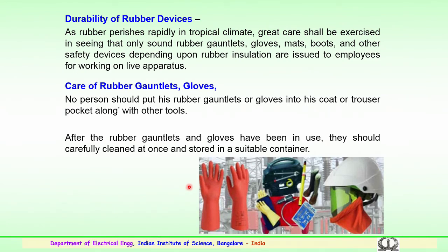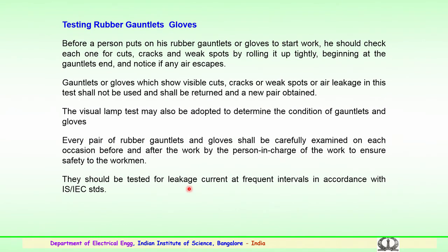After the rubber gloves or gauntlets have been in use, they should be carefully cleaned and stored in a suitable container. They should not be folded or damaged, which could create a shock if they lose their insulating properties for personnel working on live apparatus. So, these have to be properly tested at regular intervals. Special mention about the maintenance of these gloves is given in the manual of instructions to the personnel at the substation.